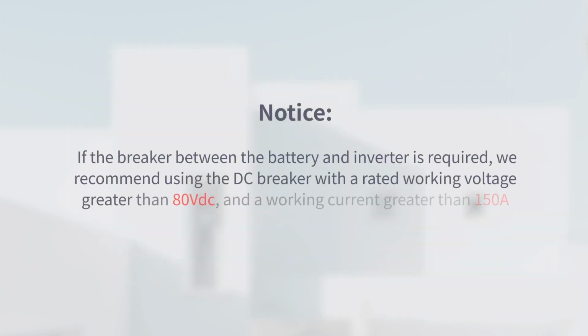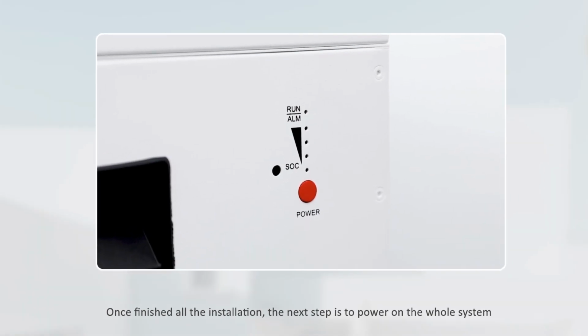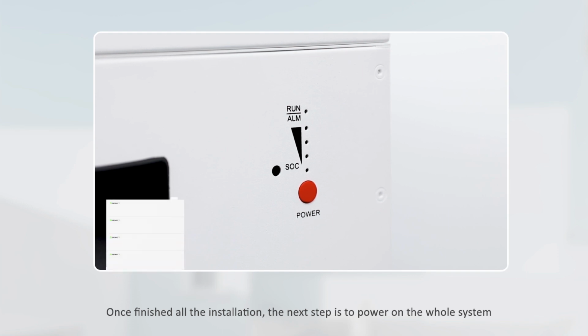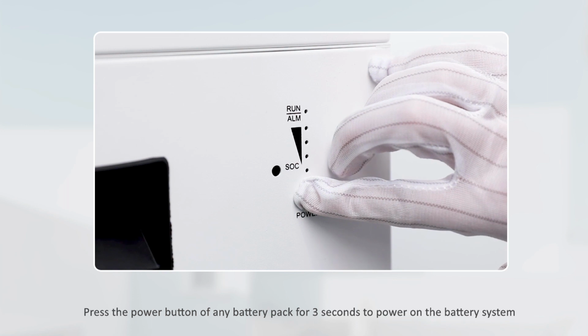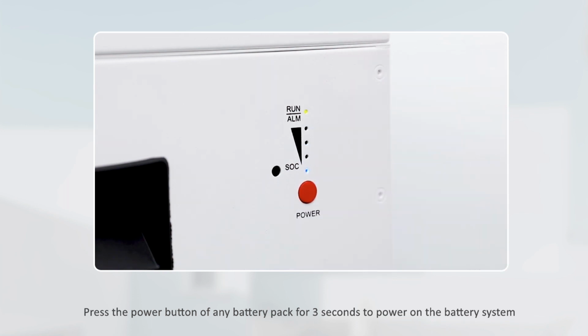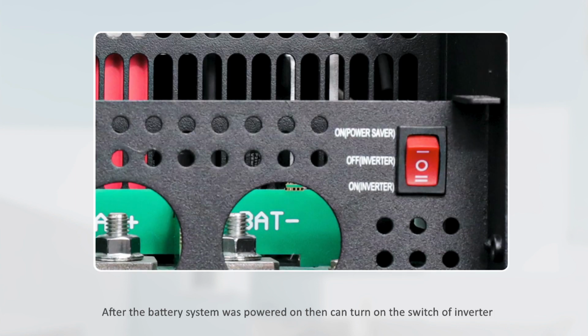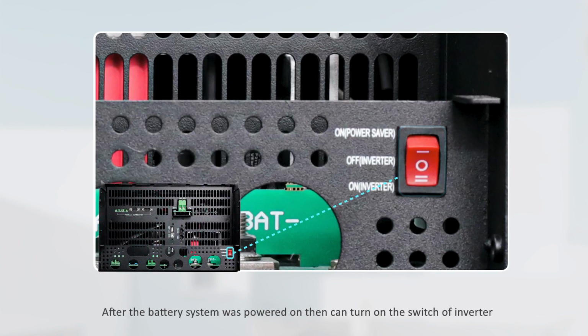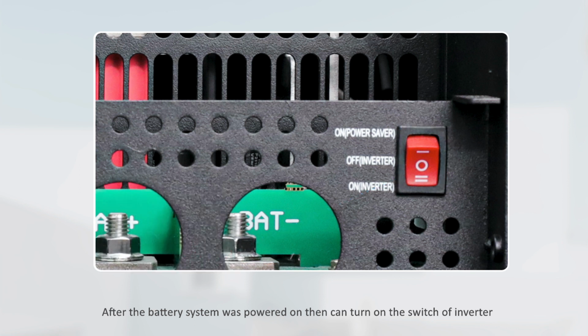If a breaker between the battery and inverter is required, we recommend using a DC breaker with a rated working voltage greater than 80 VDC and a working current greater than 150 amperes. Once all the installation is finished, the next step is to power on the whole system. Press the power button of any battery pack for 3 seconds to power on the battery system, and the SOC indicator will flicker for a short time and finally stay on. After the battery system is powered on, you can turn on the switch of the inverter.